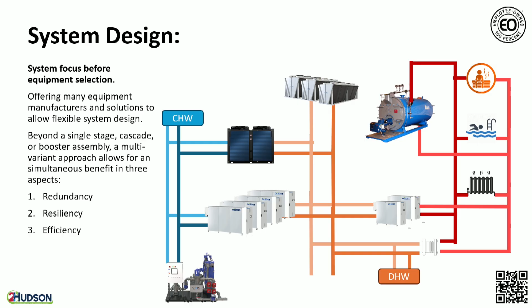Another important factor is, depending on the building you can have space heat, you can have domestic, you can have chilled water, and they will not match up almost ever. You're not going to have the same amount of chilling required as your domestic hot water. You're not going to have the same amount of space heat. And whether it's winter or summer, again, they will have peaks, and some might even be zero. And so making sure your equipment is designed for the case it's being used and not just plugging an equipment into just any use and expecting it to work. A lot of things can happen in the industry where equipment and or a way of making systems gets a bad rep because it was incorrectly installed, designed, or commissioned. And it's important to know that.